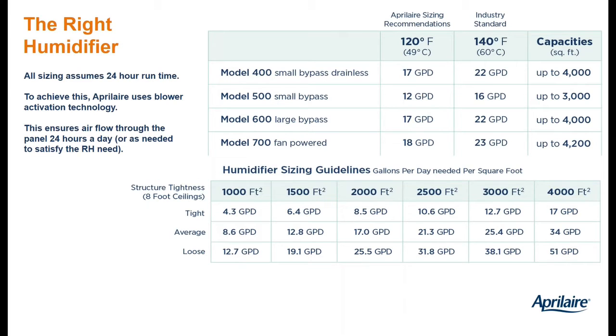We're just talking evaporative humidifiers today, and so you can see we have model 400, which is a recirculating or water conserving humidifier, the model 500, which is our small bypass, the model 600 is a large bypass, and the model 700 is our fan powered unit. That first chart is showing the amount of humidity you're going to get assuming 120 degree plenum temperature. You can see 17 gallons per day, 12 gallons per day, 17 gallons per day, 18 gallons per day.